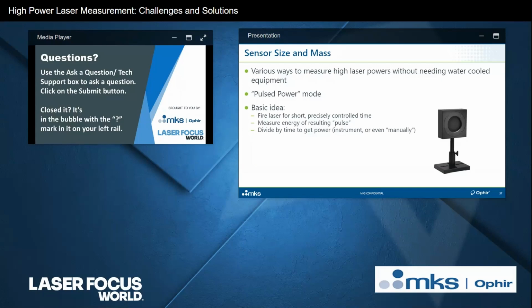But what we do is we fire this high power laser for a short, precisely known, precisely controlled time. And we treat that short exposure as what we call a single shot pulse, and we measure its energy. The sensor can do that. It might take those few seconds of response time to finish doing that, but that's fine, irrespective of how short the pulse was.